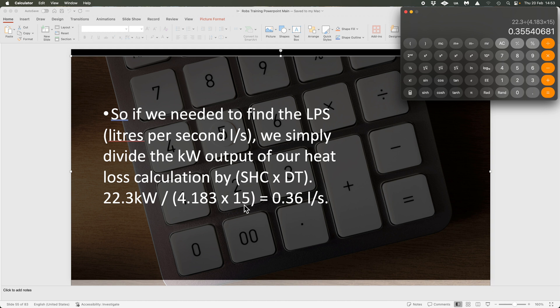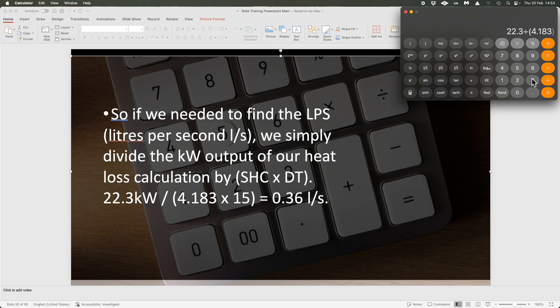Let's play around with it more. If we do it again at delta T 20 — a 70/50 system — we type 22.3 ÷ (4.183 × 20) = and we get 0.27 litres per second. You can see what's happening: going from delta T 15 to delta T 20, the actual flow rate has slowed down — there's a proportional change in flow rate relative to delta T.